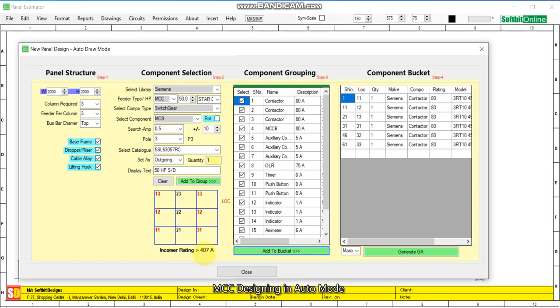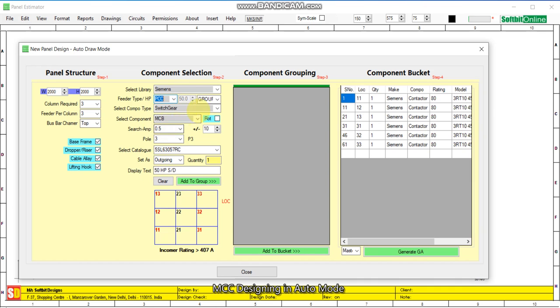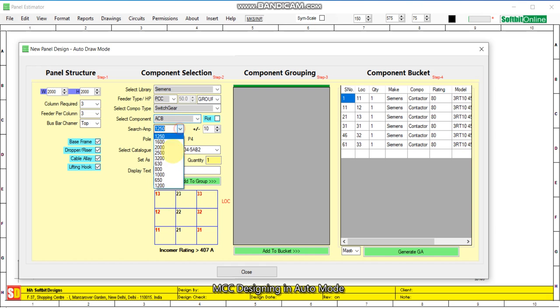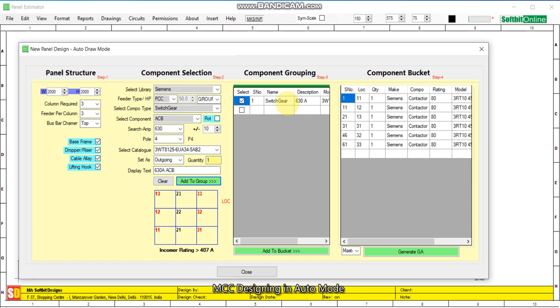Now we see the total load of all three starters is 407 amperes. So we will add an incomer rated more than this value — we will add a 630 ampere breaker. We change to power control center switchgear and select ACB 630 amp, then add to grouping zone.